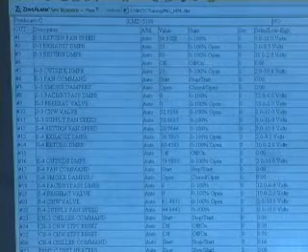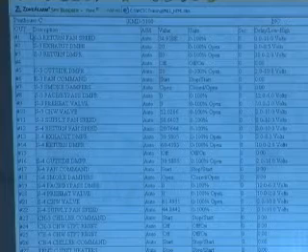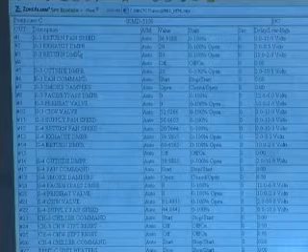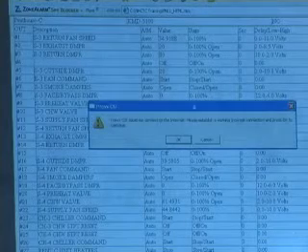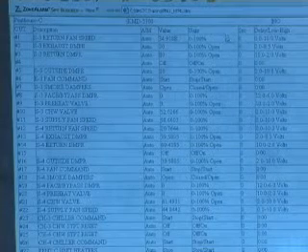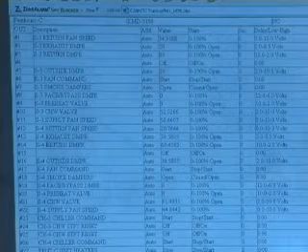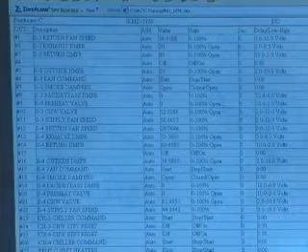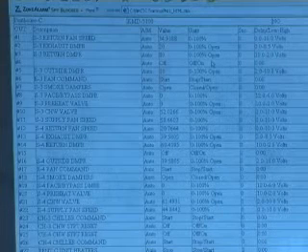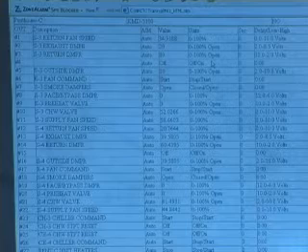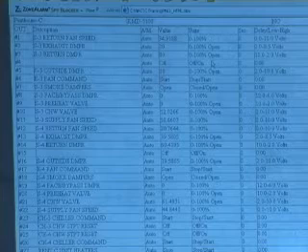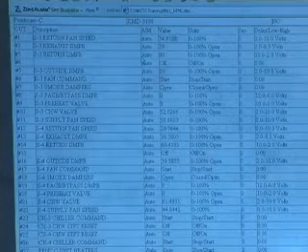This first group is outputs. These are physical outputs that are wired to the controller. So we have a VFD, an exhaust damper command. These are analog outputs, 0 to 10 volt outputs, and this is just a software label here. So when our programmer gets on site and takes a controller from scratch, when we turn on a site, this is all blank. There's nothing here. We actually type all the stuff in, or copy and paste, whatever the case may be.